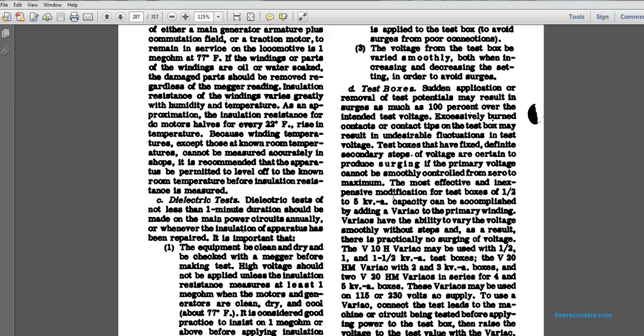Excessively burned contacts and contact tips on the test box may result in undesirable fluctuations in the test voltage. Test boxes have fixed secondary steps of voltage, which are certain to produce surging if their primary voltage cannot be smoothly controlled from 0 to maximum. The most effective inexpensive modification for the test box of 1/2 to 5 kv-a is a variac on the primary winding.